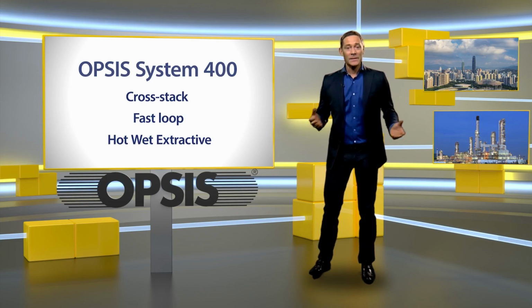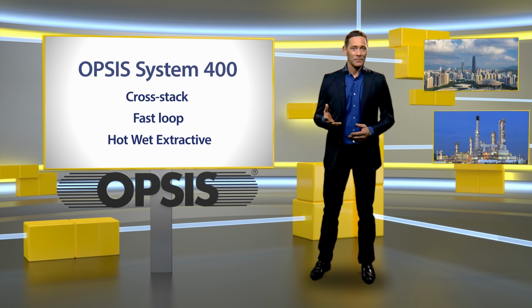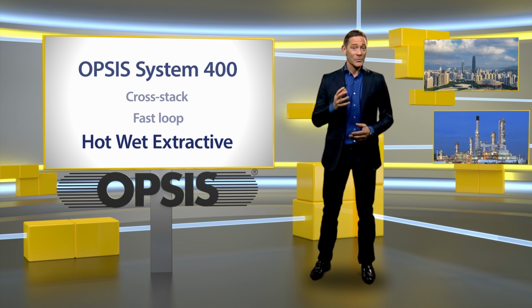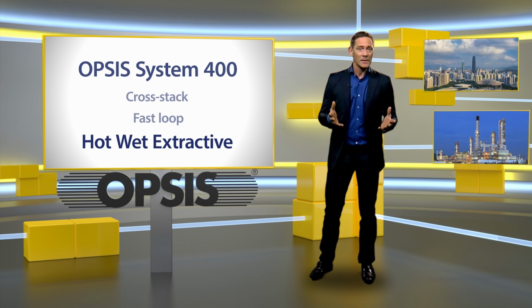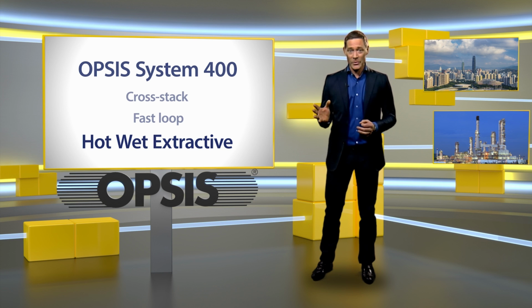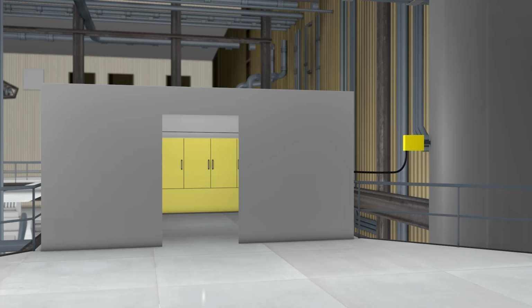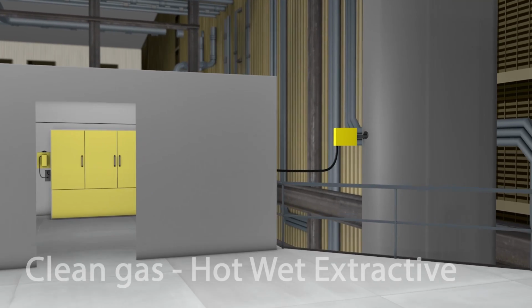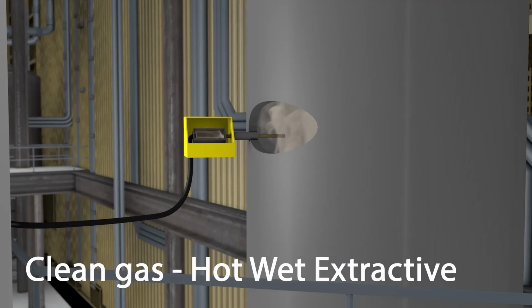In many plants, it is necessary to measure total mercury. If that is the case, then OPSIS System 400 Hot Wet Extractive is the best solution. The advantage of using Hot Wet Extractive is that in addition to total mercury, all other relevant gases can be measured at the same time. This is how OPSIS System 400 Hot Wet Extractive is installed. A sampling probe is installed in the stack.